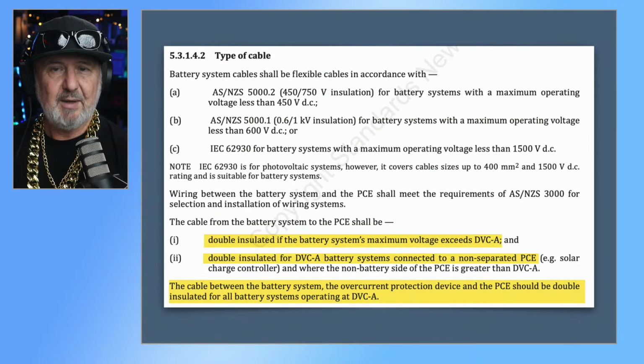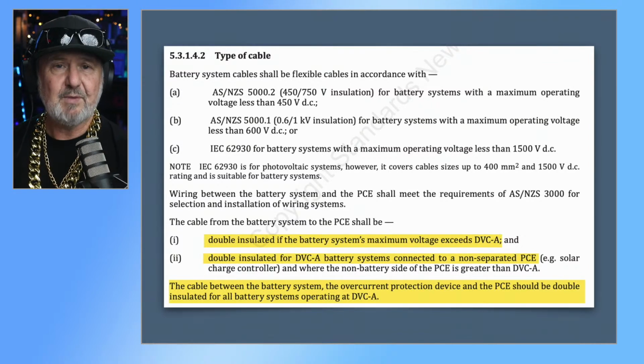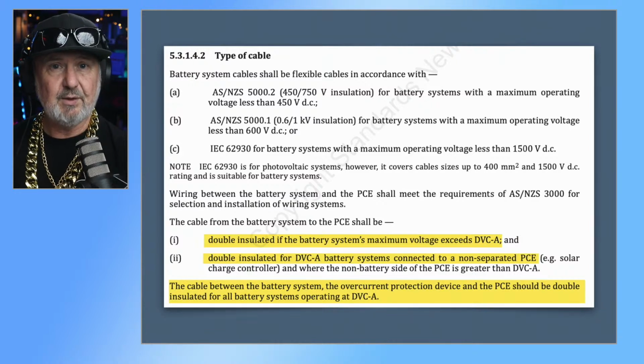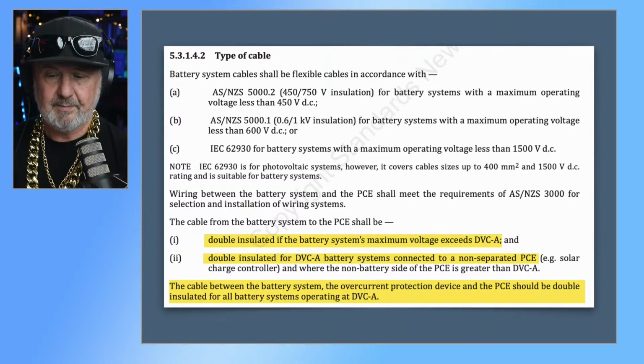Now, in our battery standard, we consider anything over 60 volts, DVC-B or C, is equivalent, this is the wording in 5139, as equivalent to an LV installation as defined by 3000. So going over 60 volts, you basically have a level of hazard that's expected to be the same as an LV installation, and therefore your requirements for protection step up.